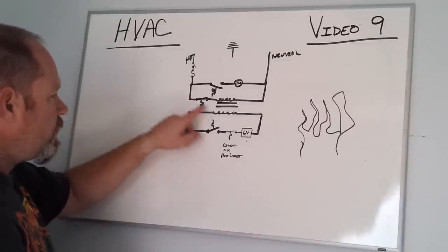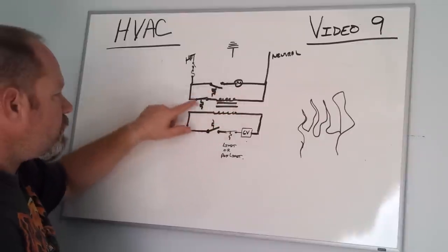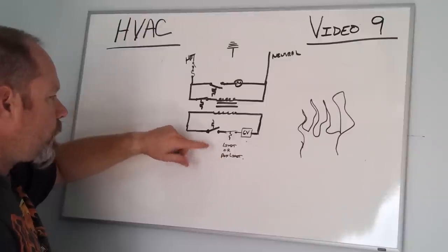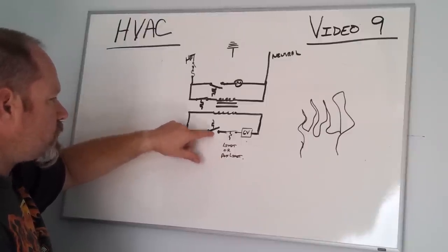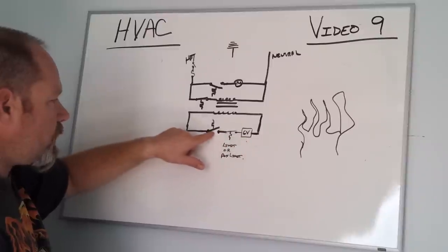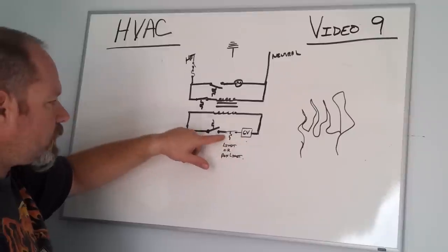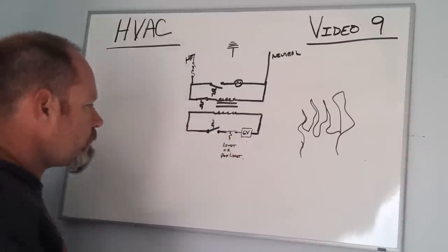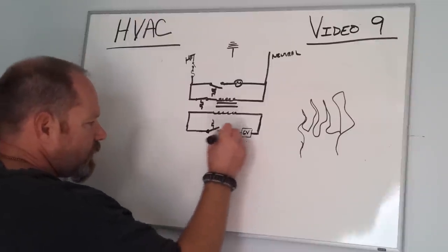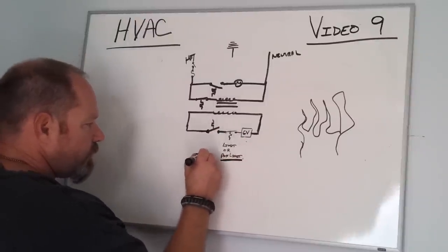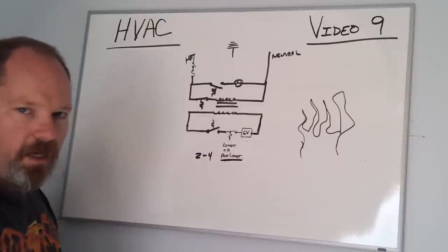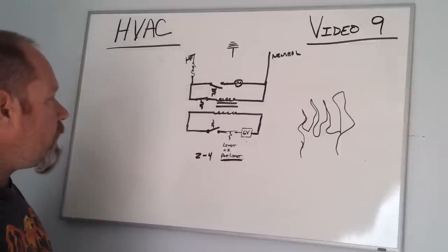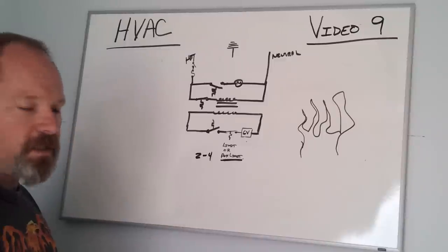And there, you have a fan switch to turn the fan on, you got a limit switch to protect from overheating, and it shuts the entire 24-volt system off. You have a thermostat that'll turn the gas valve on when the temperature drops. And you also have a limit control that is going to turn the fire off if something happens. Typically, in the limit control or the auxiliary limits, you may have up to 2 to 4 of these in different locations, depending on which type of unit you have. Okay, so this is a basic ladder diagram of a furnace, a simple basic standing pilot furnace.